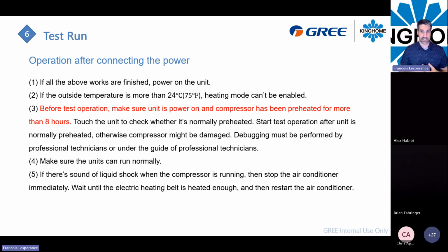Also, the heating mode will be disabled if the outdoor temperature goes above 24 degrees Celsius. And the reverse, it's not on the slide here, but cooling is not enabled when it's minus 15 degrees Celsius. So don't try to use the heat mode if it's 30 outside. The system will just not go on.